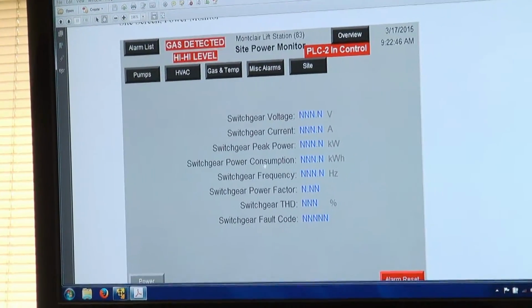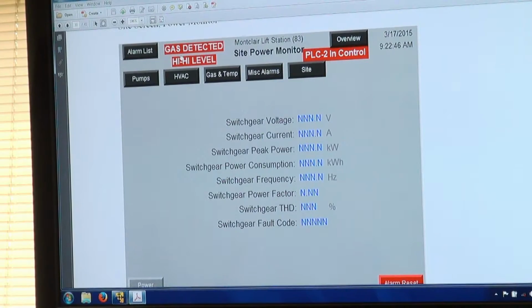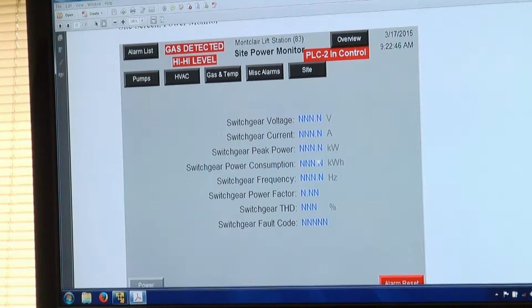Finally, this is the power monitor. I kind of left it in development mode, so that's why all these are N's. They're actually numbers, but you can see here's your gas detected, here's your high level, and here's what it looks like if PLC 2 is in control. It's no longer blue, it's a big red symbol that says something's wrong with this PLC 2. And these three are going to be on every page that you're at.